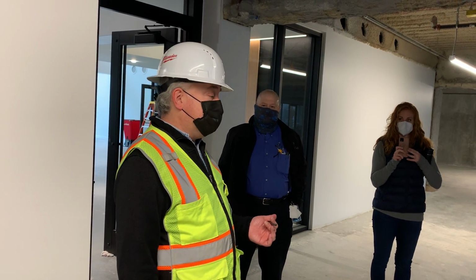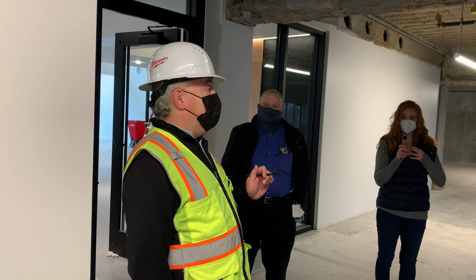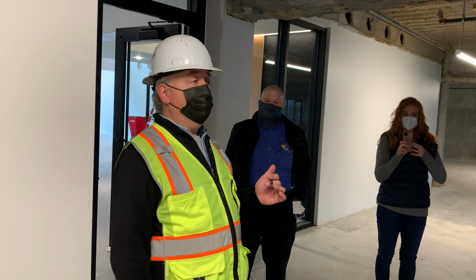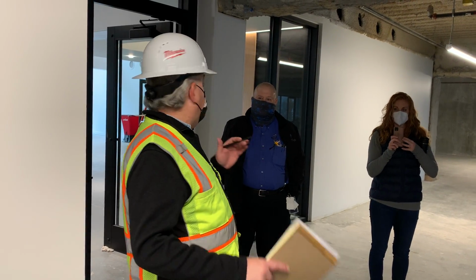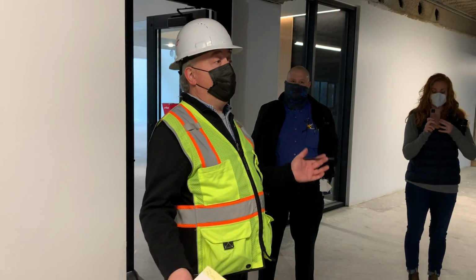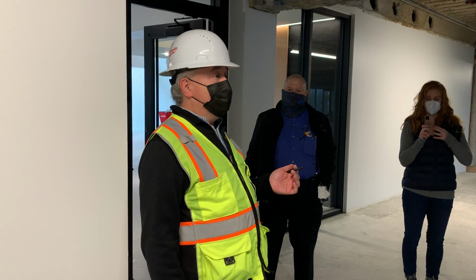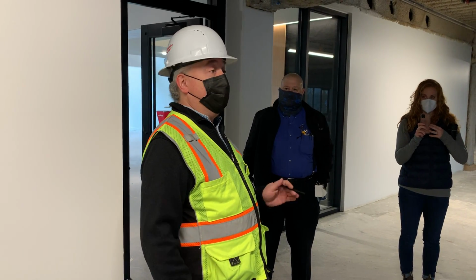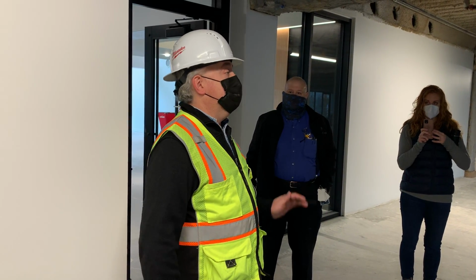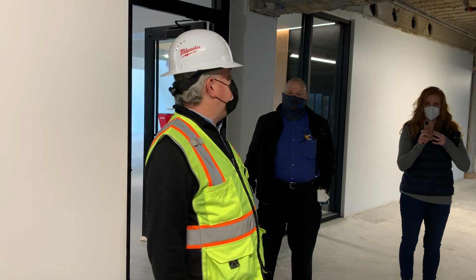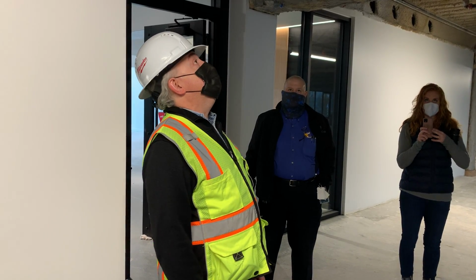The current sequence of operation is 8 a.m. to 6 p.m. weekdays. All of the lighting that you see on right now is on and remains on. Outside of those hours, it's controlled by occupancy sensors. There are no override switches in the space currently. It is strictly sensor controlled after hours.